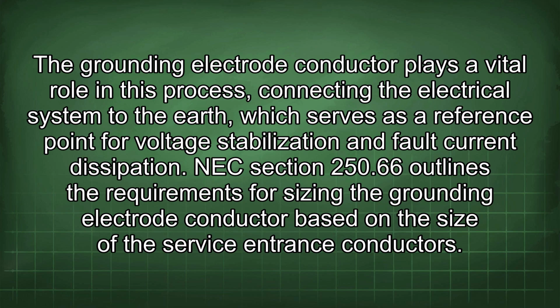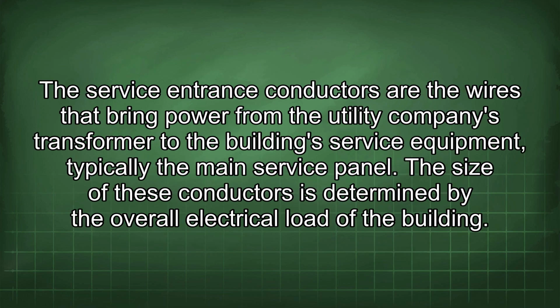NEC Section 250.66 outlines the requirements for sizing the grounding electrode conductor based on the size of the service entrance conductors. The service entrance conductors are the wires that bring power from the utility company's transformer to the building's service equipment, typically the main service panel. The size of these conductors is determined by the overall electrical load of the building.